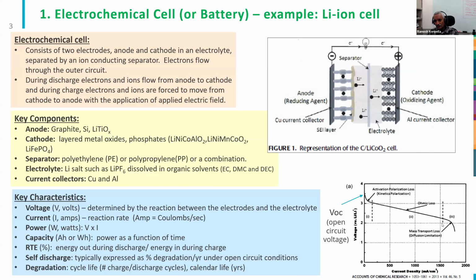If you go very high, you could run into a bad condition, because when you're drawing current from the battery, you also generate heat. The heat comes from the inefficiency of the battery - how much energy you're discharging versus how much you put in. You want very high efficiency. Lithium batteries operate at 85% to 90% efficiency, but that means still 10% inefficiency converted into heat. If you're drawing too much power, it could generate a lot of heat that leads to unsafe conditions, so you want to avoid that.